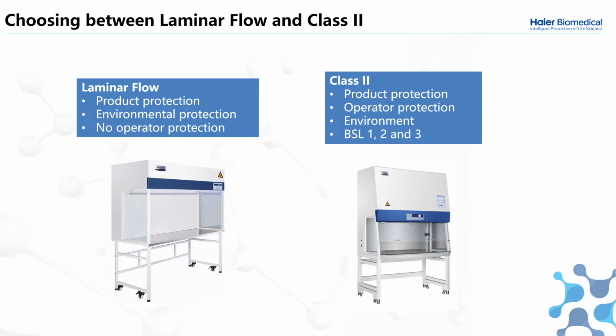With a laminar flow, the only protection offered is product protection and environment protection. However, there is no operator protection. There is no filter or airflow protecting you from contamination or from any dangerous products inside the clean bench. The class 2 cabinet offers you product protection with a downflow, operator protection with the recirculating front flow, and environmental protection with the HEPA filter, which filters all exhaust coming out of the cabinet. In our NSF models, it will be a ULPA exhaust. And these are appropriate for biosafety levels 1 through 3.